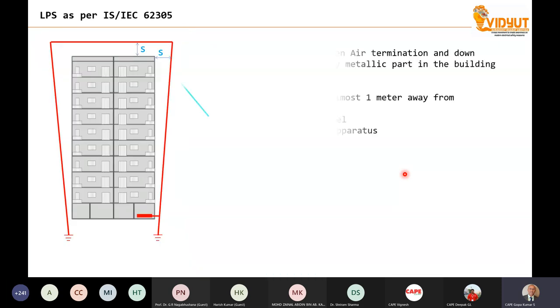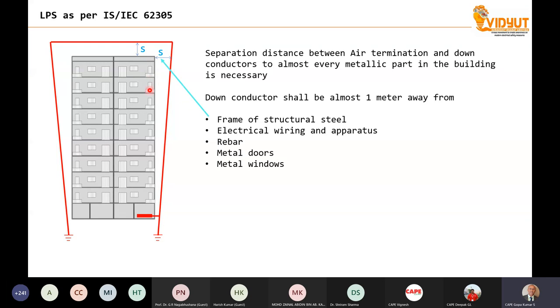What does it mean is, you have the building here, and this red color is the air terminal, air termination and down conductor, and the S stands for the separation distance. In order to avoid spark over, flash over, between different objects, down conductors shall be at least, for example, 1 meter away from the frame of the structural steel, electrical wiring, rebar, metal doors, metal windows, and so on.